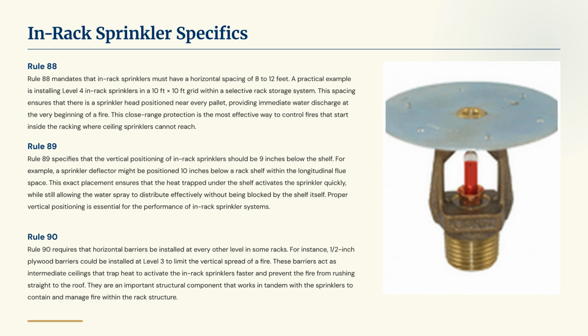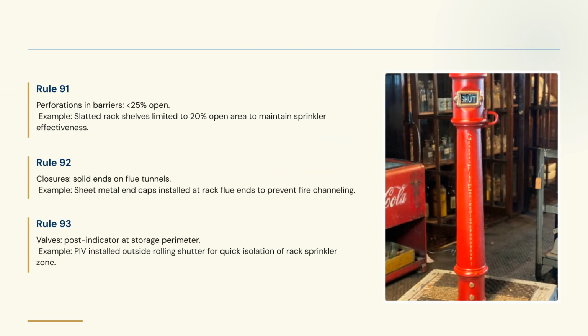Rule 89 specifies vertical positioning should be 9 inches below the shelf. Rule 90 requires horizontal barriers at every other level in some racks to limit vertical fire spread. Rule 91 limits perforations in barriers to less than 25% open area. Rule 92 requires solid end caps on flue tunnels.